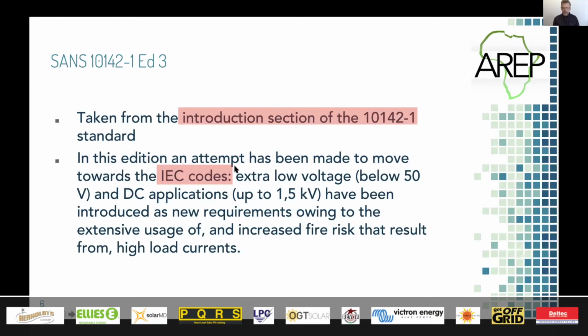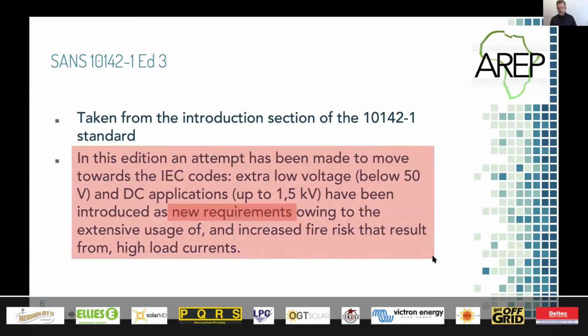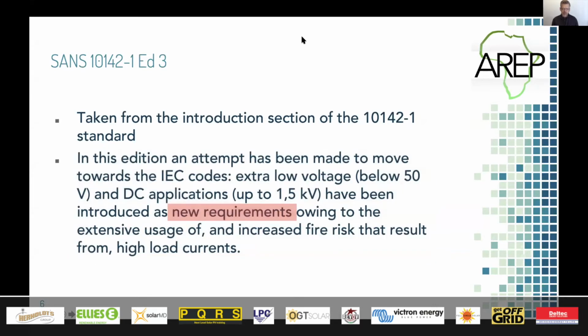So we'll see a lot of IEC codes being adopted by the SABS. It also says extra low voltage, below 50 volts, and DC applications up to 1,500 volts have been introduced as new requirements owing to the extensive usage and increased fire risk resulting from high load currents. Although it says new requirements here, this part of the introduction into the standard, I think, has been in there for almost the last 10 years. So it's not new news, but unfortunately nobody really takes the time to read the introduction into standards - we want to get through to the juicy stuff.